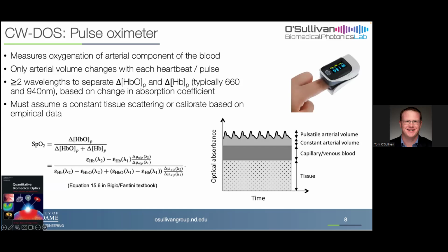That can work if you have a good representation of the population, right? If you have a good representation of the pathology of the population, right? If you've got someone who perhaps has some sort of disorder related to blood flow, for example, they're not going to be represented. It's only going to work in a particular range that you calibrate. So doctors know this, or doctors should know this, that the pulse oximeter is really a binary measure. It's either good or it's bad, right? The difference between 92% and 93% is meaningless, right?